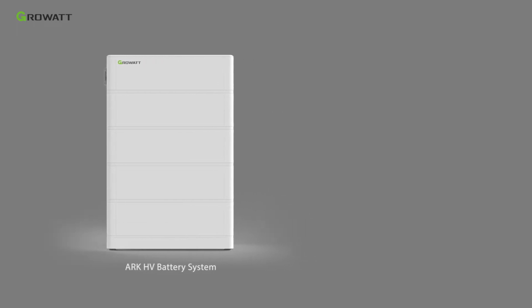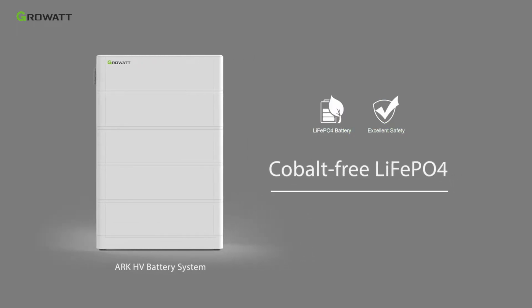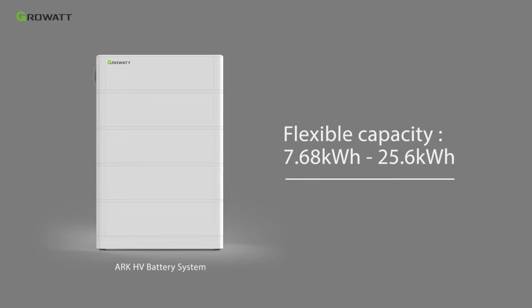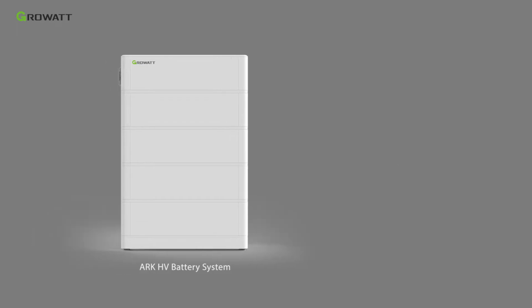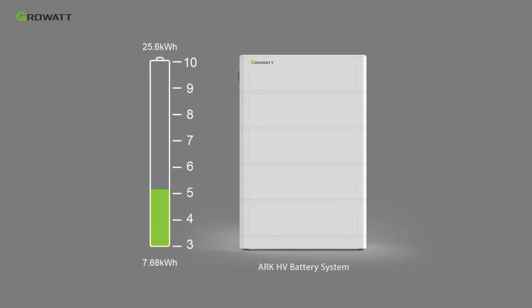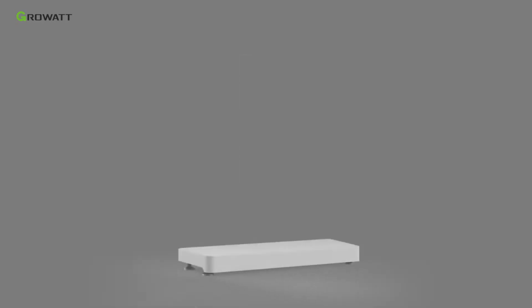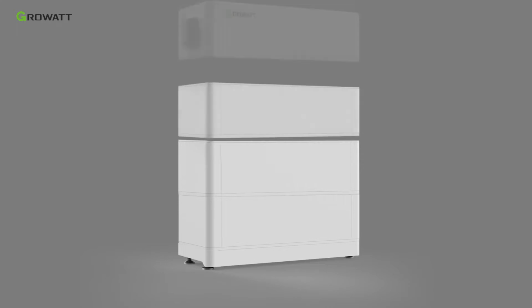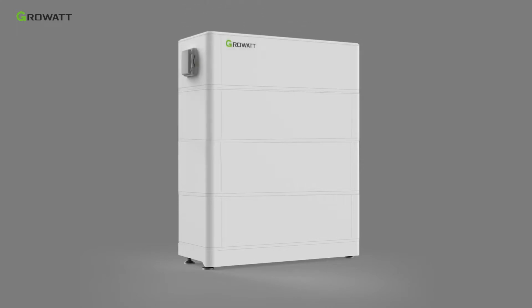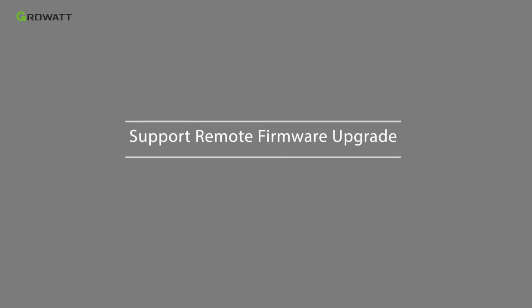ARK battery uses cobalt-free lithium iron phosphate to guarantee its excellent safety, offering flexible capacity options for customers. Each battery module is 2.56 kWh, and supports 3 to 10 pieces in series, covering 7.68 kWh to 25.6 kWh. The whole system is easy to install with a modular and stacked design. It supports remote firmware upgrade to save on-site maintenance fees.